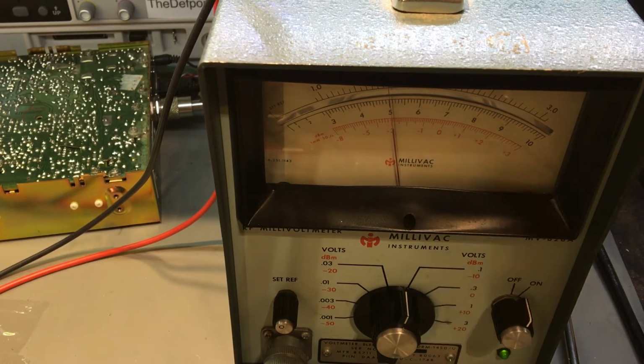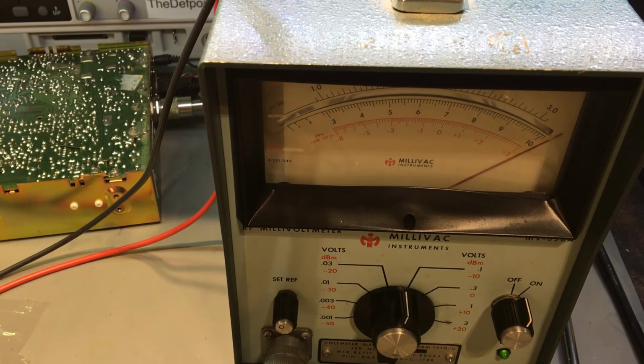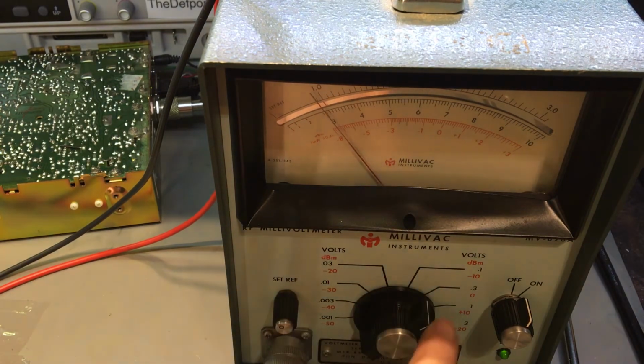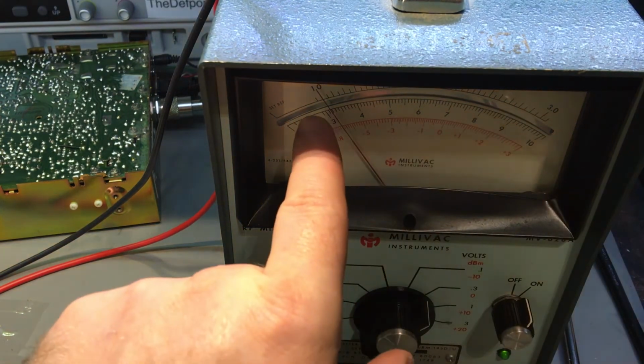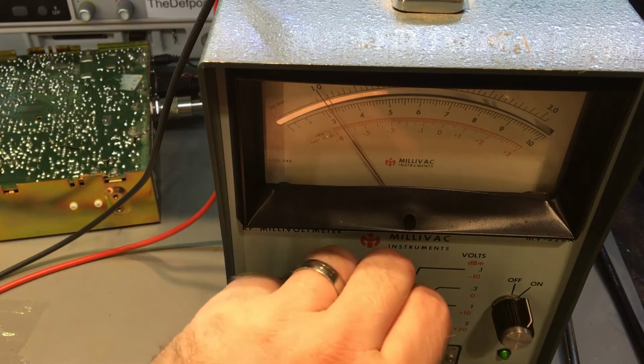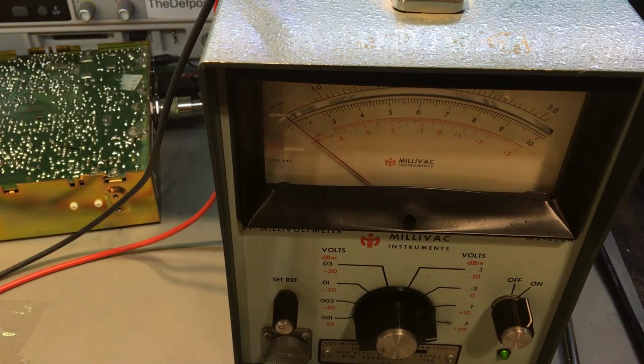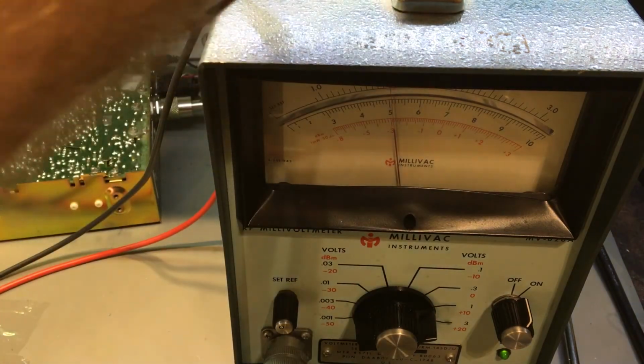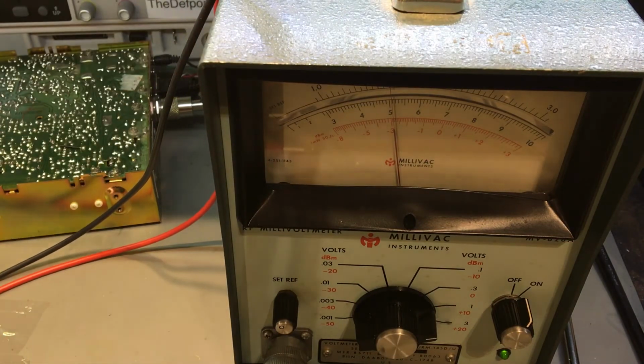So if I'm going to set this at 100 millivolts, it's pretty much full scale, so yep, it is. So if I go to the 0.3 range, that should be 1, it is. If I do the 1 volt range and I go to 0.5 volts, so 500 millivolts, that's pretty much right, as is my Fluke over there saying the same thing.